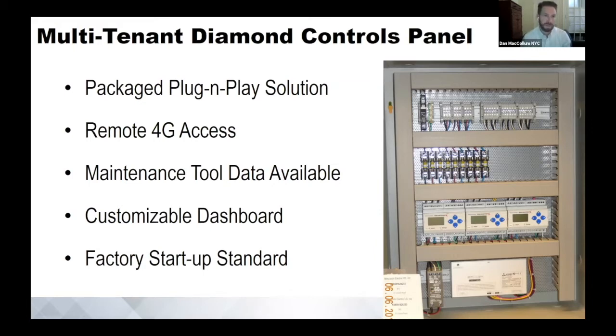But some of the added benefits from this packaged solution that weren't available previously are 4G remote access to the system, and maintenance tool data becomes available even remotely. Maintenance tool data is what contractors use to troubleshoot, diagnose, and service Mitsubishi VRF systems. So if you have a multifamily passive house building and there's a problem system or a problem unit, your contractor can log in remotely before they even roll a truck. They can look at the outdoor unit, indoor unit, BC controller, trended operating data, and they can have an idea of what they're walking into before they even pack up their truck and head to the site. So it gives a new window of information to the contractor or even to the building owner in terms of how the system is operating.